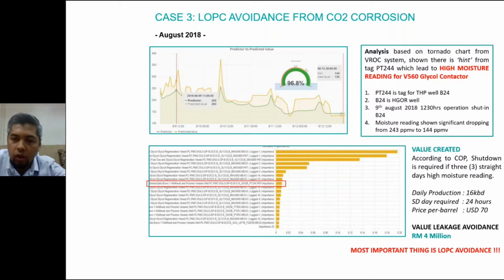things that we need to take care of is the amount of water inside the gas, which is the moisture in it, because the high moisture would cause CO2 corrosion, and CO2 corrosion internally would get that particular pipe to leak, right, and cause safety issues. So Dulang is required to keep this moisture below 200 ppmv.